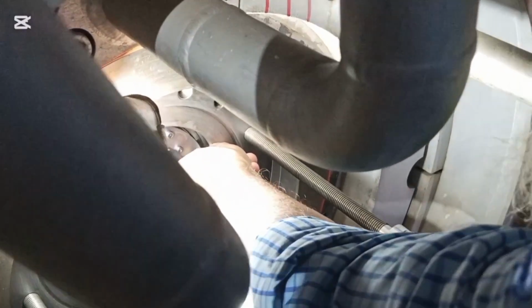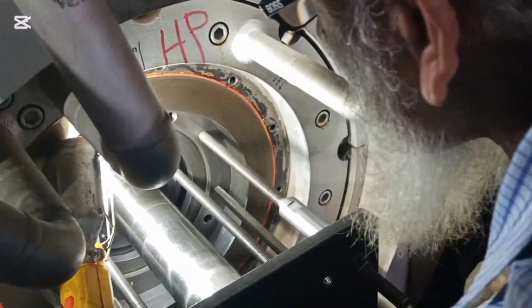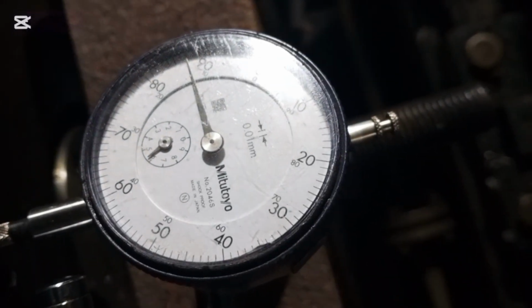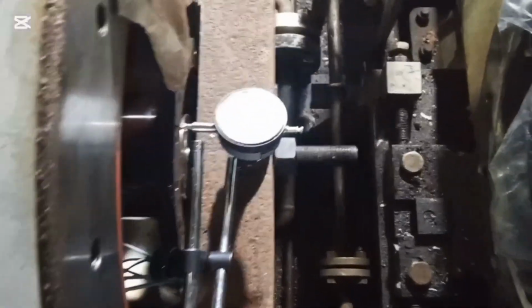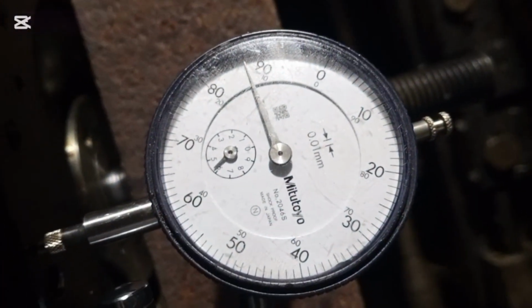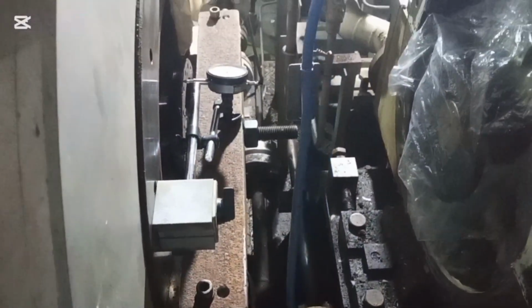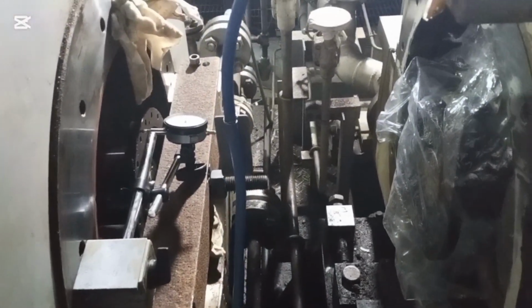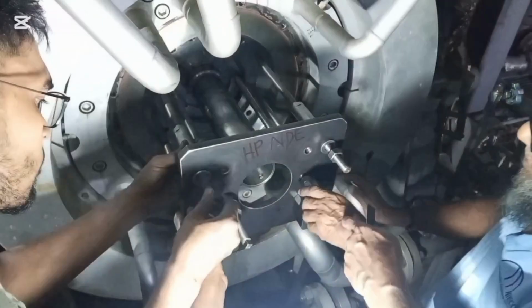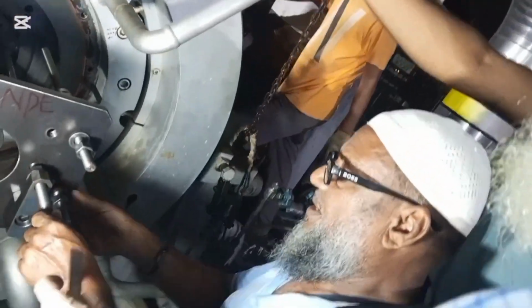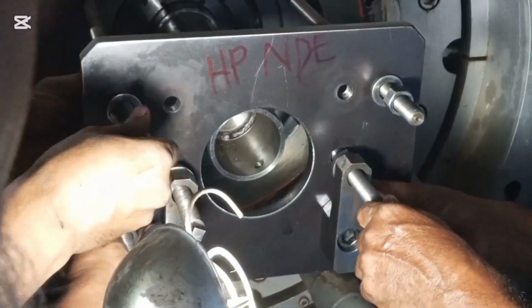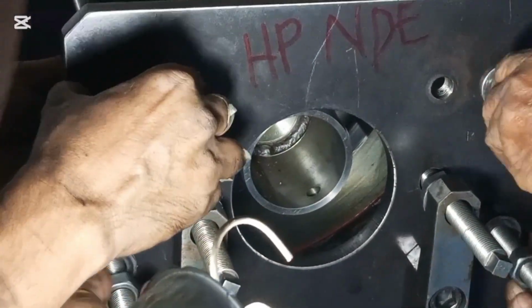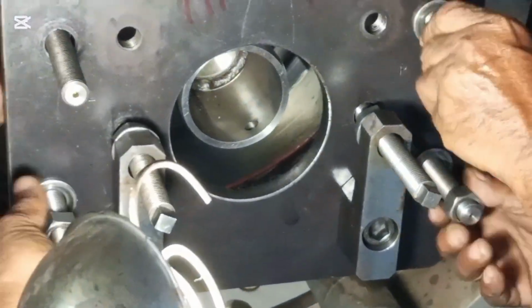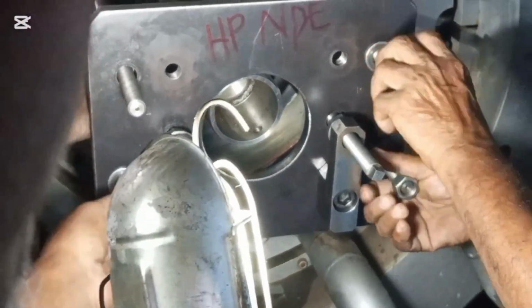And then journal bearing and thrust bearing were fitted also very carefully, sequentially one after another. After that, the instrumentation works and other works were done. For the instrument sensors and instrument items, at first we connected the cable, and then we followed the reading from our control room, and if the reading varied, then we adjusted the probe as well as the proximeter. And after that we connected all the instrument items and then covered the compressor.